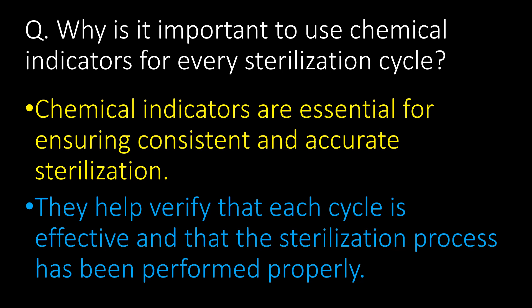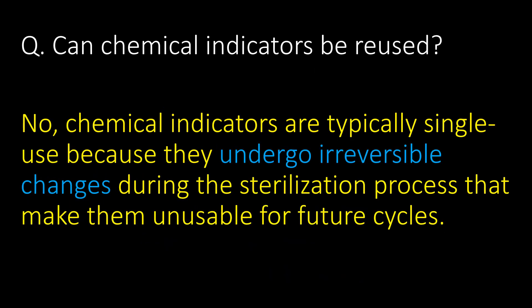Why is it important to use chemical indicators for every sterilization cycle? Chemical indicators are essential for ensuring consistent and accurate sterilization. They help to verify that each cycle is effective and that the sterilization process has been performed properly. A very frequently asked and important question: can chemical indicators be reused? The direct answer is no. Chemical indicators are typically single use because they undergo irreversible changes during the sterilization process that make them unusable for future cycles.